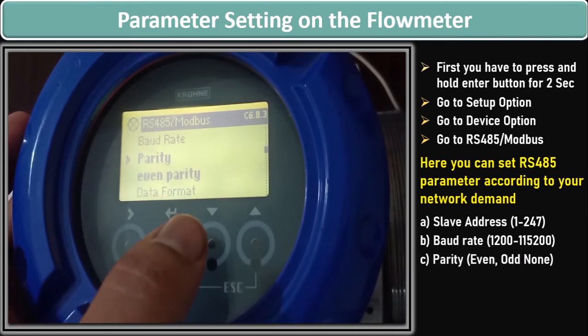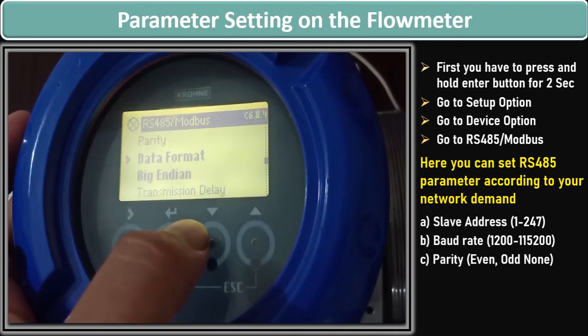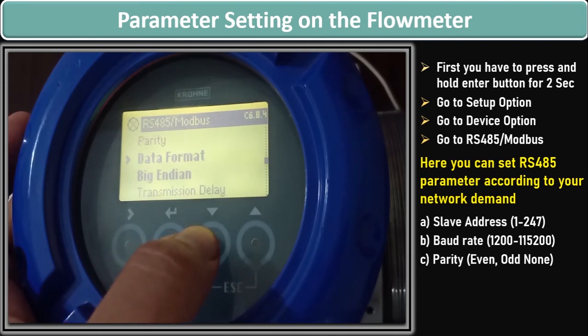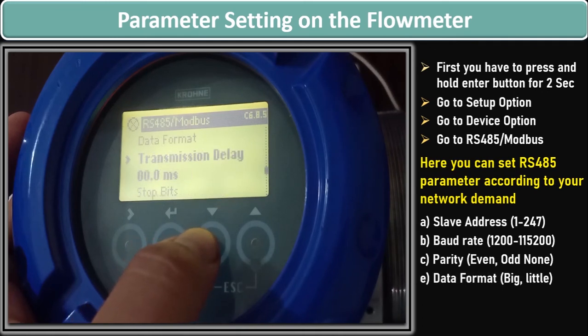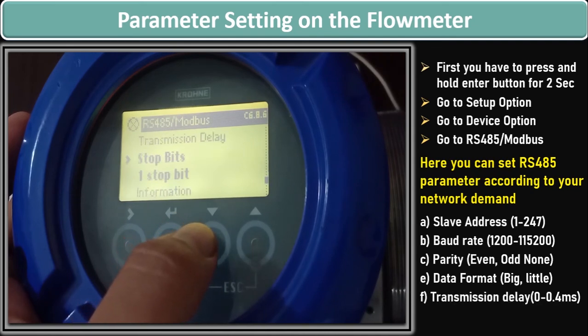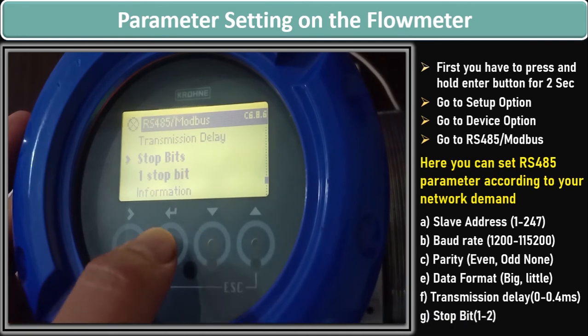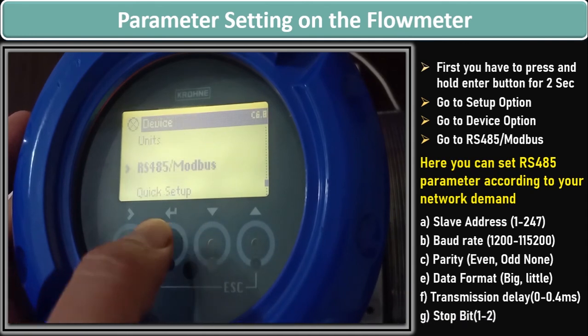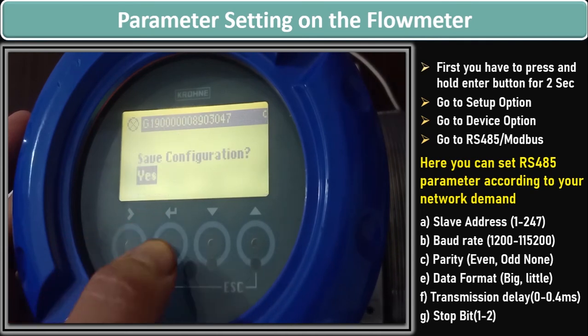Similarly, you can see the parity — at the moment parity is set to even. Then we have the data format option — at the moment data format is big endian. Then we have a transmission delay — at the moment it is set at 0.0 ms. And lastly we have the stop bit, which is set as one stop bit at the moment. After checking all the settings, we go out of the setup by pressing the escape button.